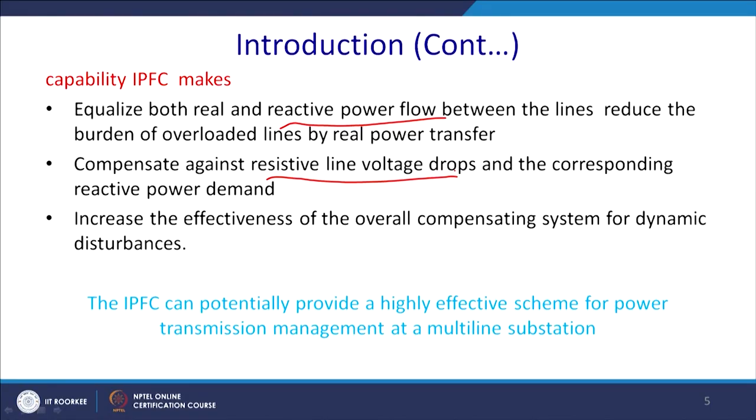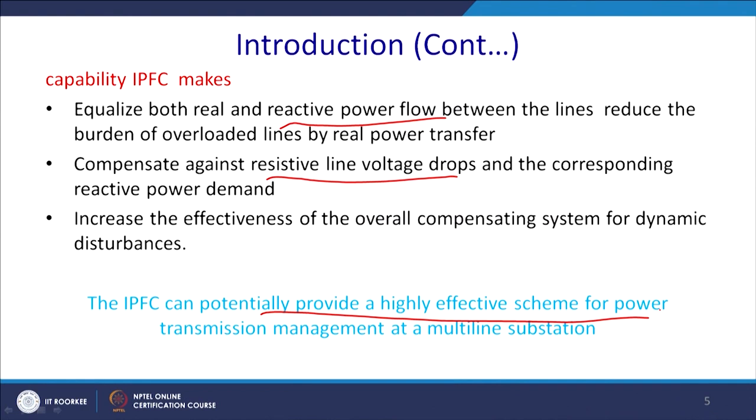IPFC compensates against resistive line voltage drop and corresponding reactive power demand without changing the X/R ratio. It also increases the effectiveness of the overall transmission system against dynamic disturbances because if there is a sag in a particular line, it can respond very fast compared to series or shunt compensation alone. Thus, IPFC can potentially provide a highly effective scheme for power transmission management of a multi-line substation.